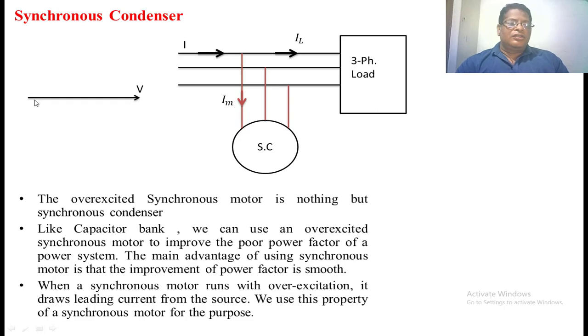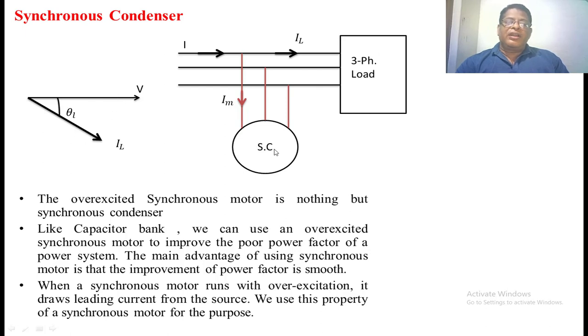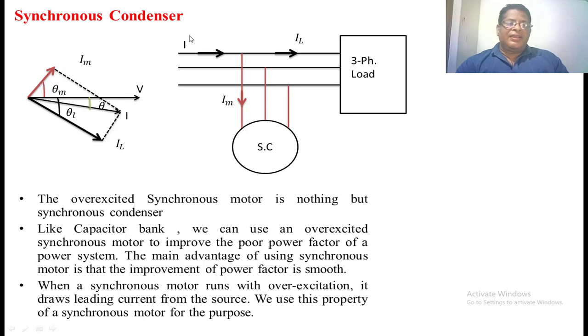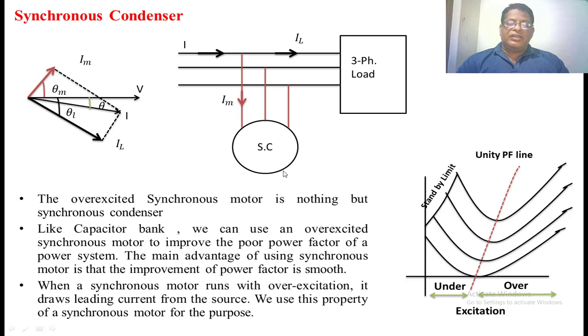This can be seen in the phasor diagram. We take voltage V as the reference. The load current IL lags the voltage by angle θL. When we connect a synchronous condenser across the load, it takes a leading current IM. The resultant of IM and IL gives the net supply current I. The angle between the voltage and this resultant current I is reduced, so the overall power factor is improved.